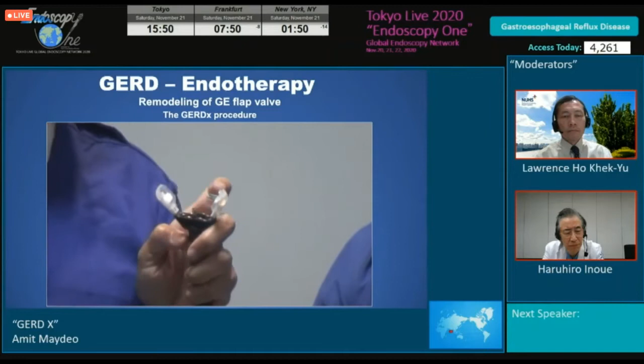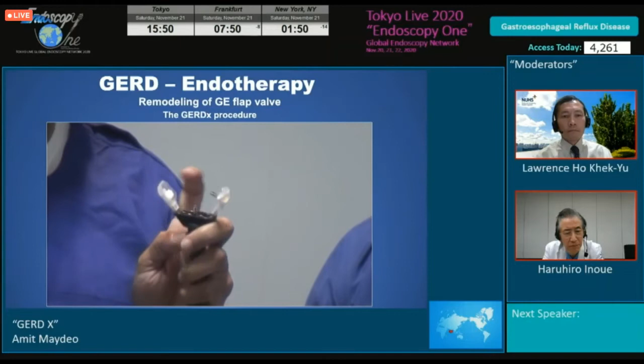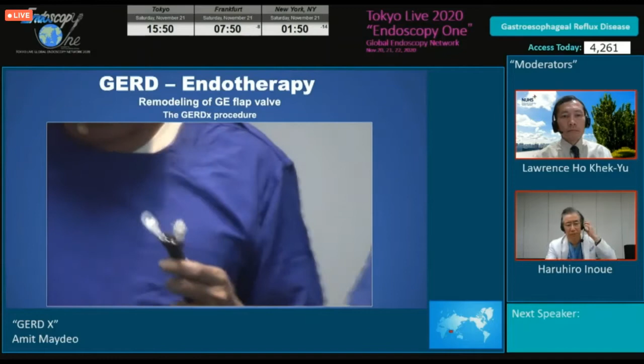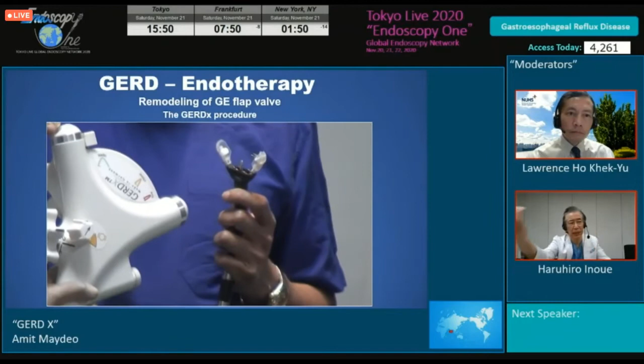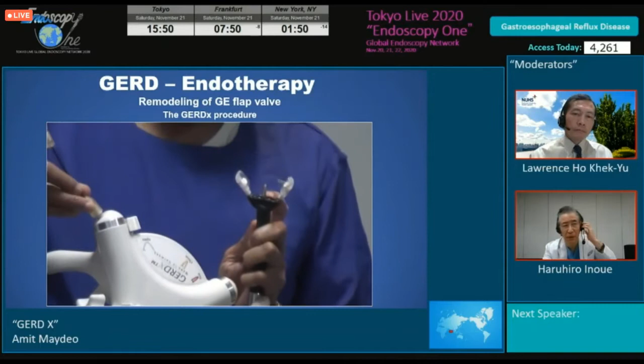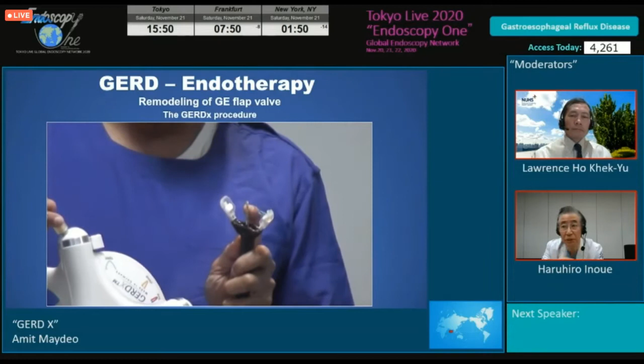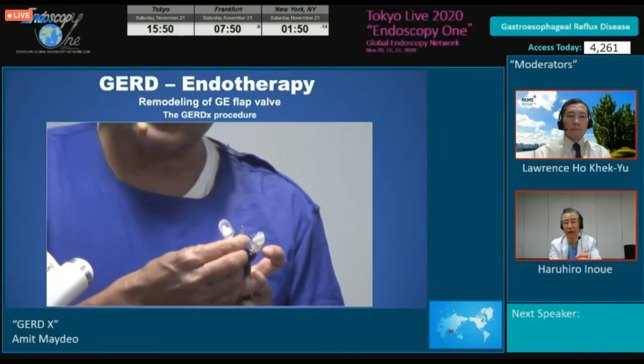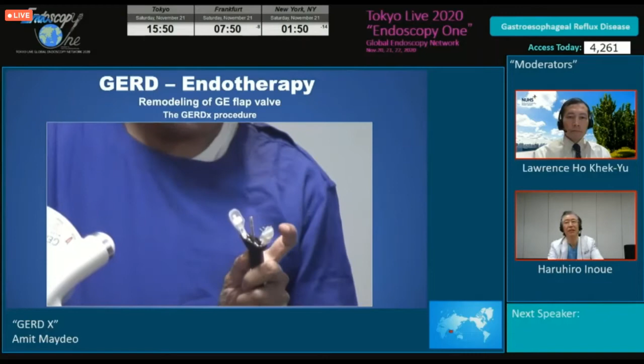Now to apply the staple completely through and through the tissue, we have to pull the wall of the stomach between the two arms. So in the middle of these two arms, you can see this small channel through which we can pass inside a spiral-shaped helix. This preloaded helix is now pushed inside through this small channel and it comes out between the two arms of the GERDx device. You see that the helix is coming out. It is covered with a plastic sheath, which is basically for protection. However, the plastic sheath goes back when you push the helix against the wall of the stomach, and the spiral enters the tissue. So after catching the tissue, we have to pull the tissue between the two arms of the device.